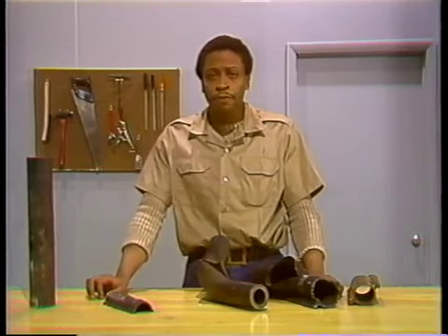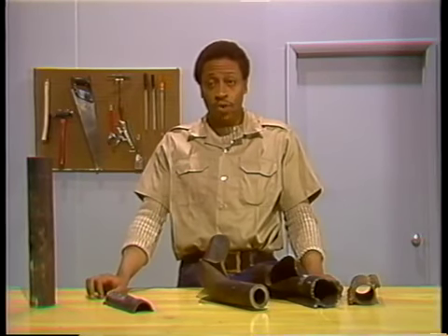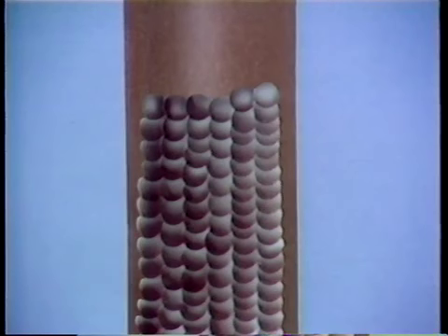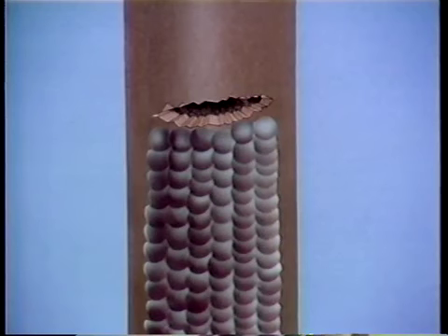Tearing of the tube metal at weld patches is also caused by mechanical stress. This occurs when the weld patch and the tube expand or contract at different rates. Contraction can stress the metal so severely that it tears open. This kind of failure can mean that the wrong kind of material was used for welding the patch.